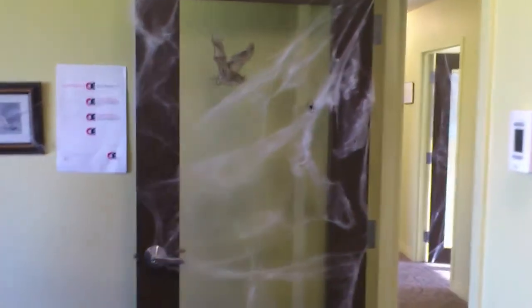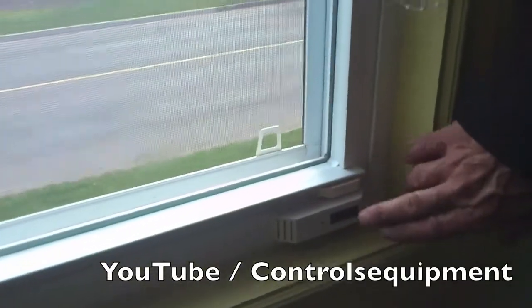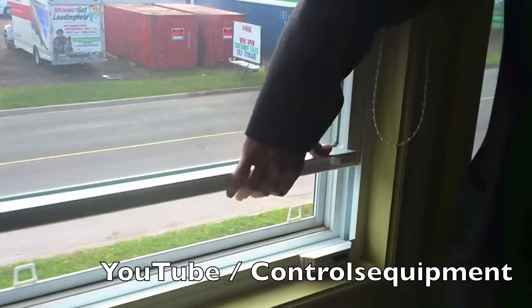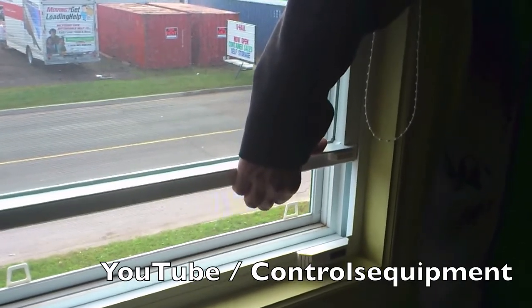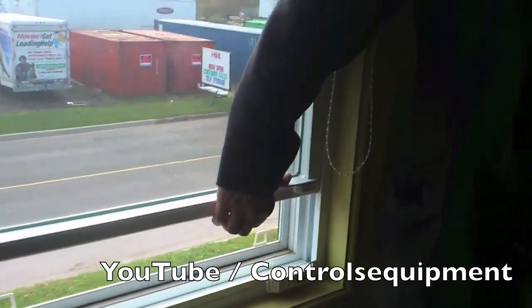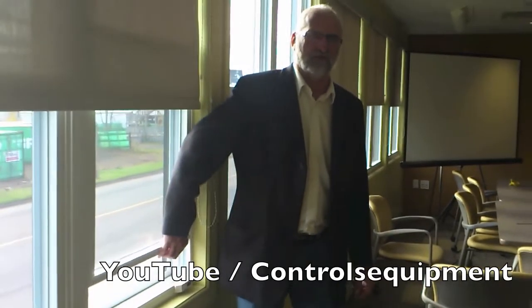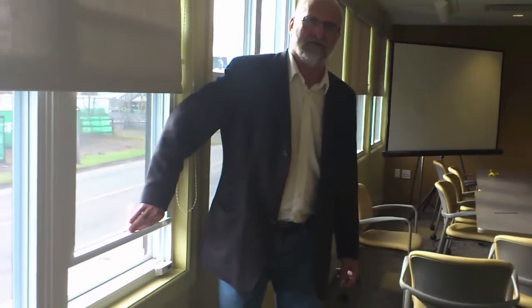Now I'll show you where the tie-in of the window contacts are with the room thermostat and the VAV in the room. Here's an example of a window contact — wireless, batteryless, solar-powered. When we open up the window, the contact is broken and the thermostat will go into an unoccupied mode, turning off all external heating and cooling. If you want free air, we're not going to supply you with mechanical cooling or hot water heating. It's a very good way to save energy.